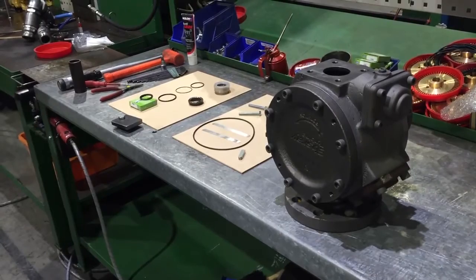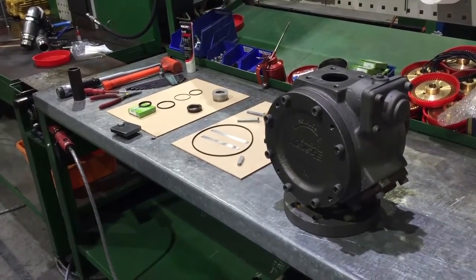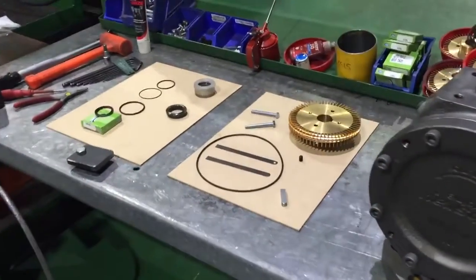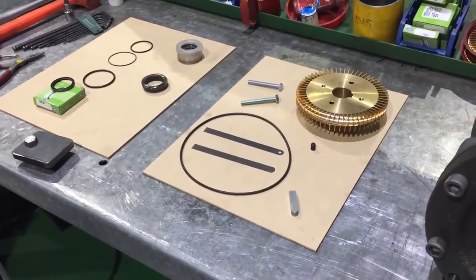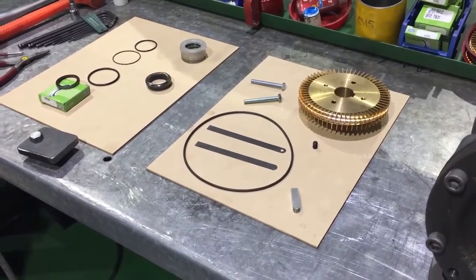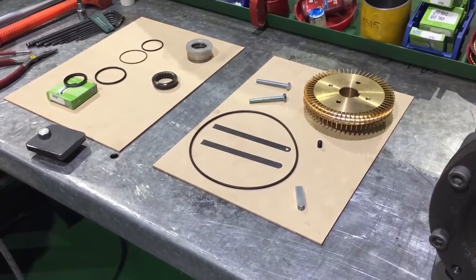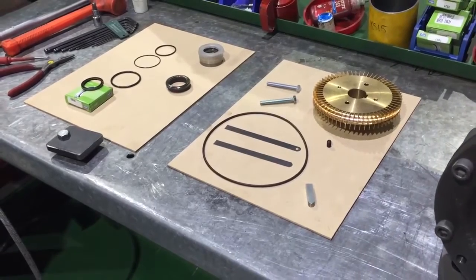This video demonstrates the procedure for removing and replacing the turbine impeller and mechanical seal. The impeller replacement kit comes with an impeller, an impeller key, an M8x12 socket set screw, a cover O-ring, two M8x75 set screws, and two four thousandths of an inch or 0.1 millimeter feeler gauges.